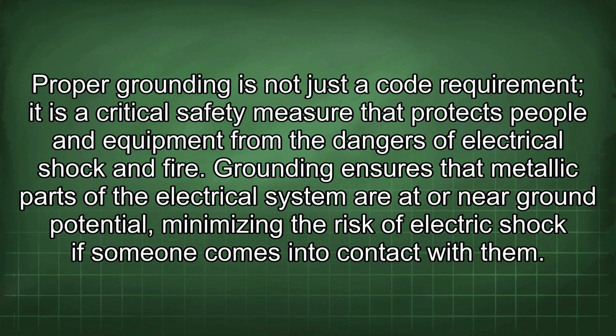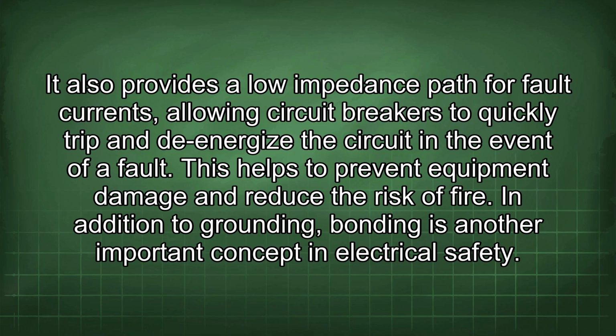Grounding ensures that metallic parts of the electrical system are at or near ground potential, minimizing the risk of electric shock if someone comes into contact with them. It also provides a low impedance path for fault currents, allowing circuit breakers to quickly trip and de-energize the circuit in the event of a fault. This helps to prevent equipment damage and reduce the risk of fire.